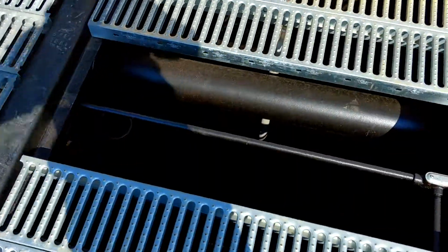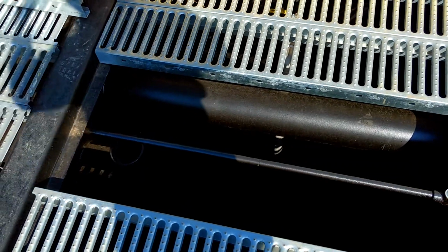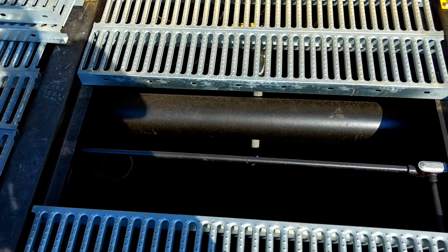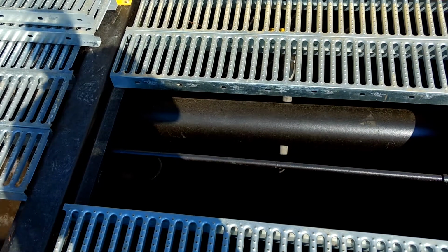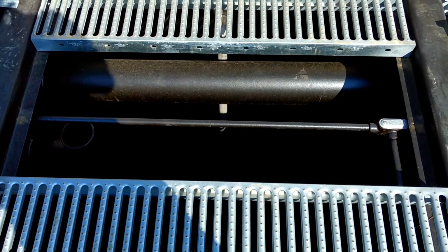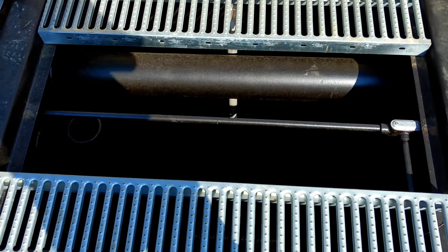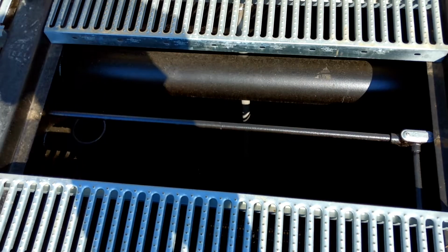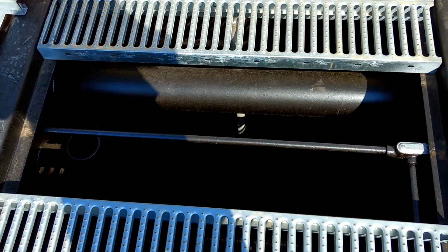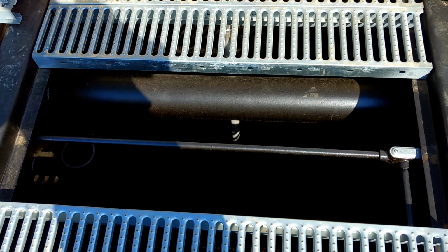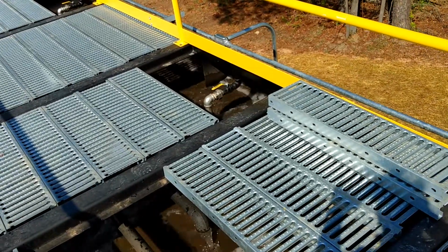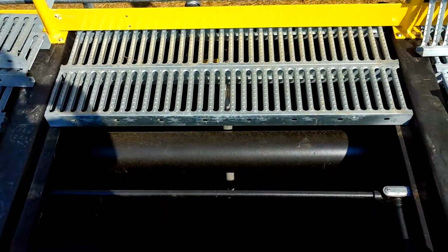And as I mentioned earlier, the byproduct of wastewater treatment is waste sludge. Waste sludge is nothing more than excess bacteria, and they are pumped here to the sludge holding tank. When the sludge holding tank becomes full, it is decanted, that is to say the clear water on top after the sludge is settled, is pumped back into the aeration chamber, thereby lowering the tank, and you can waste more.